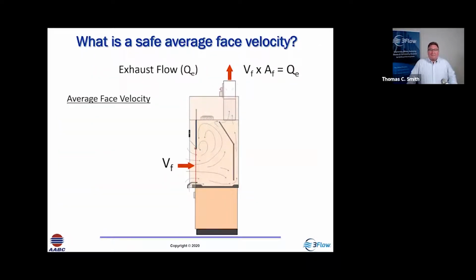But hoods are fairly complicated. They're what's called a complex hood, a compound hood that has an opening based on the sash position. Vertical sashes go up and down. Horizontal sashes go left and right. But this happens to be a vertical sash. And we know then the simple math that velocity times the area of the opening equals the exhaust flow. And those are values that we're all very familiar with.